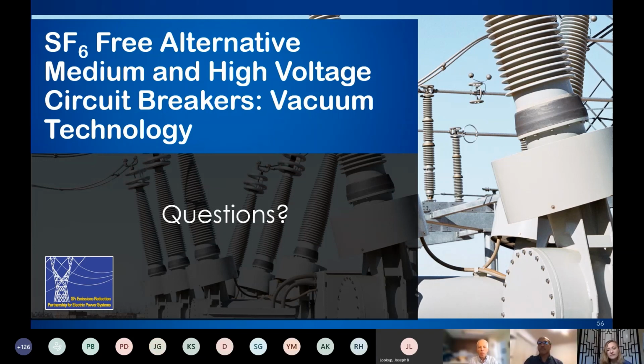Yeah, hi, this is Brian Farmer again. Well, of course, there are always contingencies on that. It depends on the rating of the breaker and the manufacturer, so there's not one single answer, but we're finding around 15% so far. I think as you get to higher voltages, that differential may increase, but it's a little hard to tell because a lot of the breakers are still in the development phase and not really commercialized yet. We only have one commercial product really available right now.